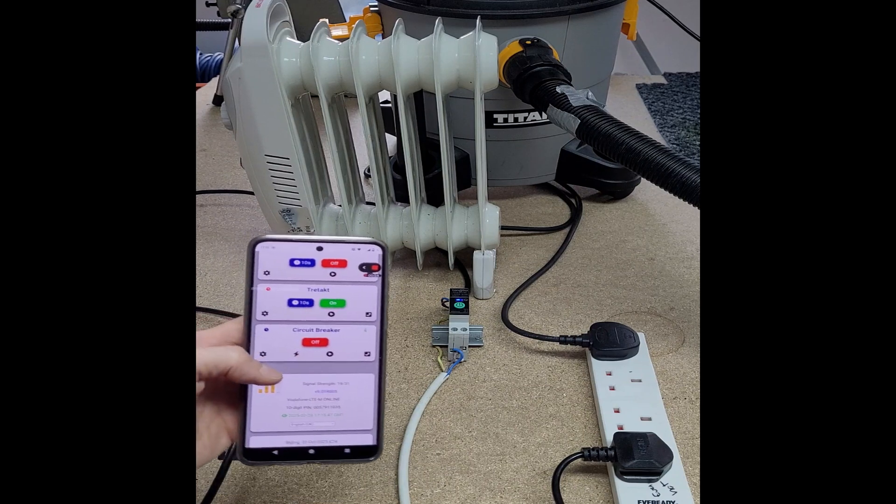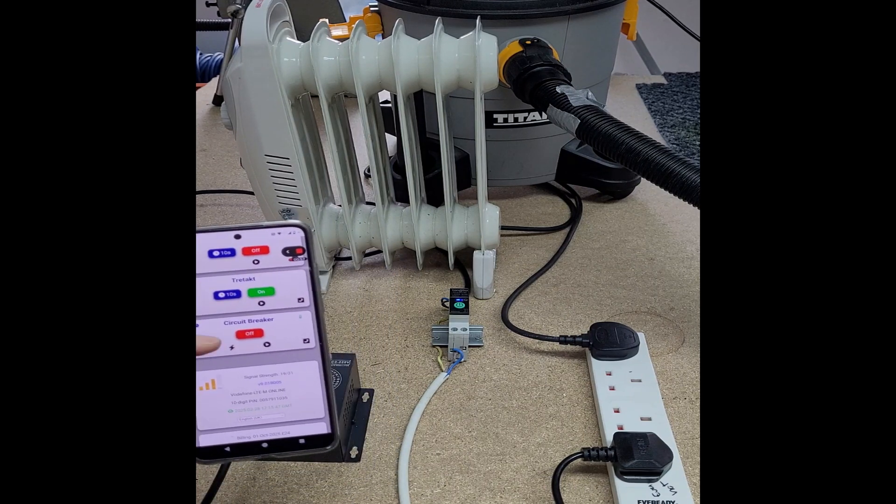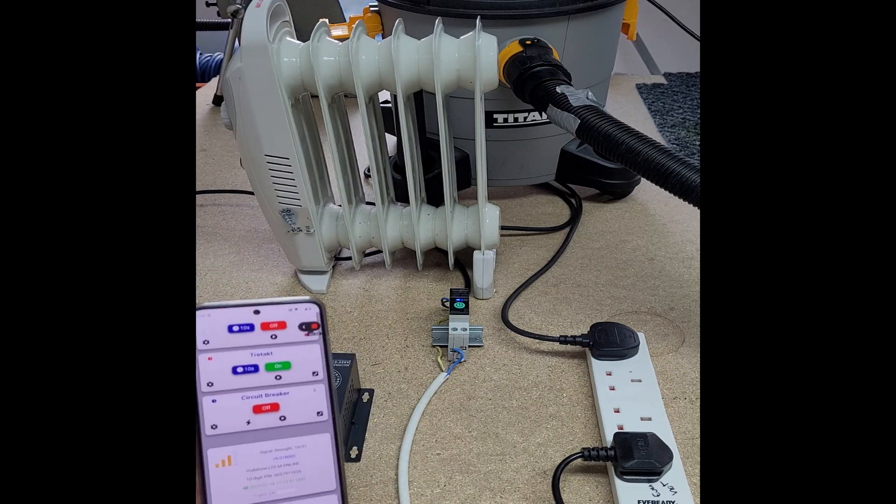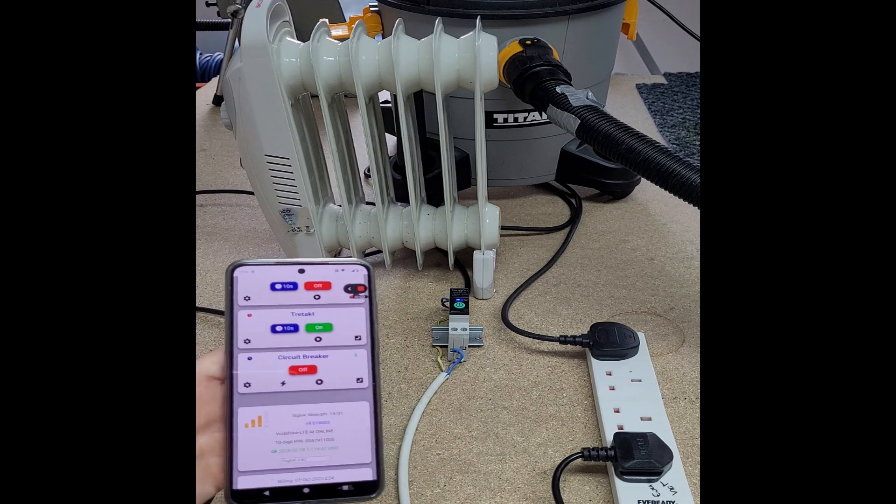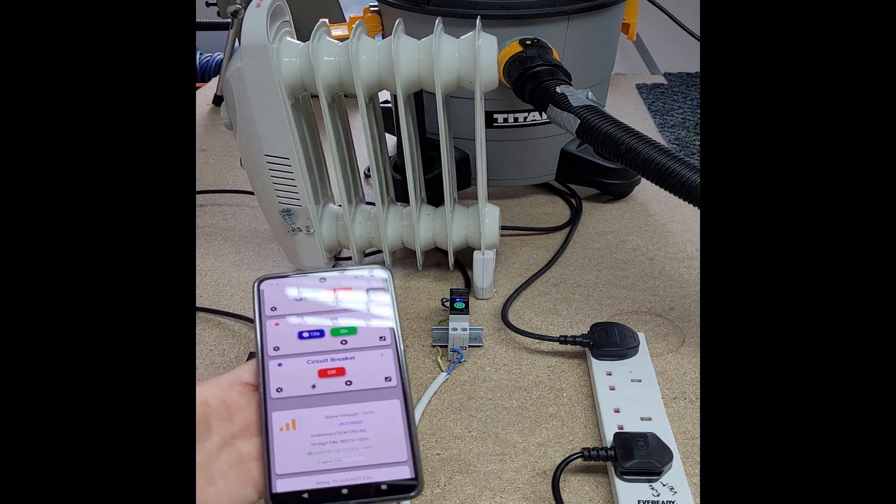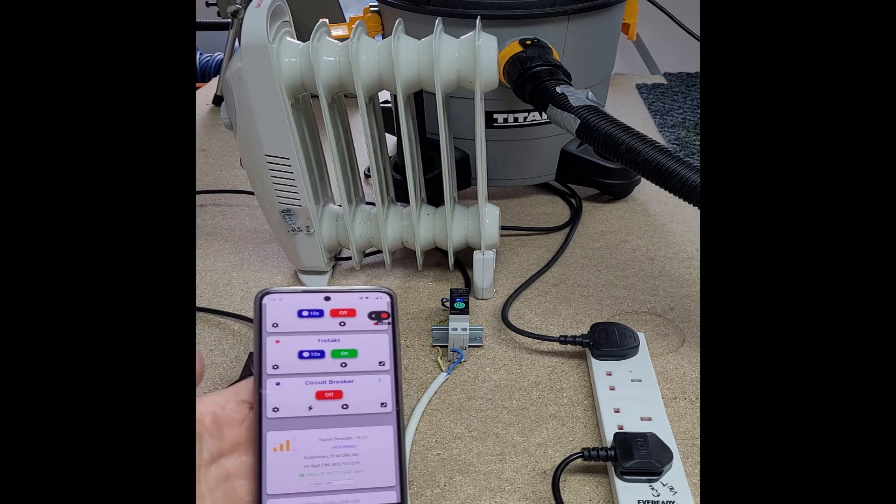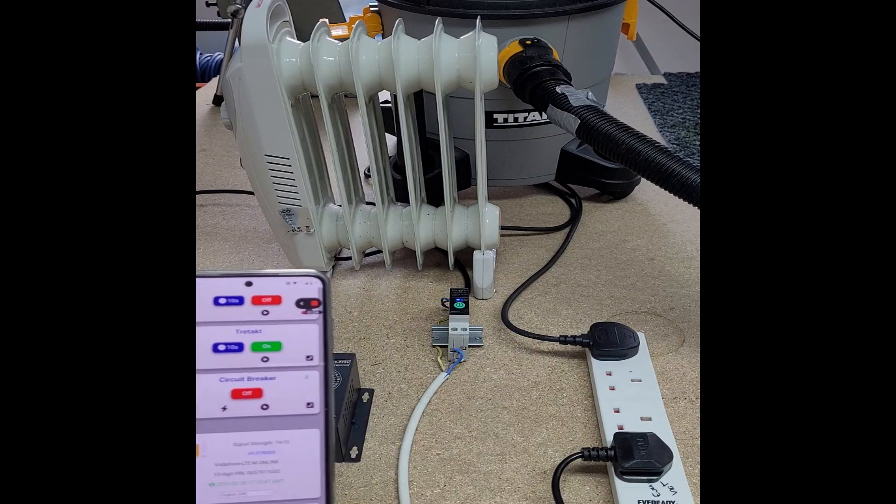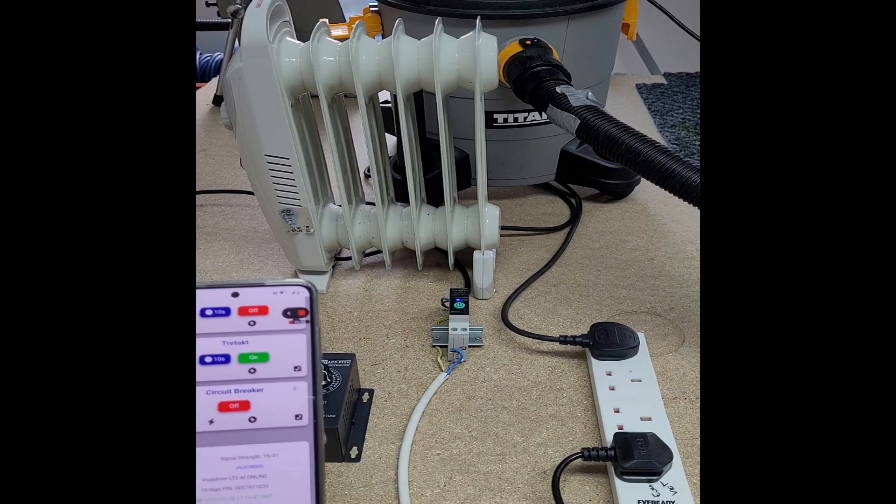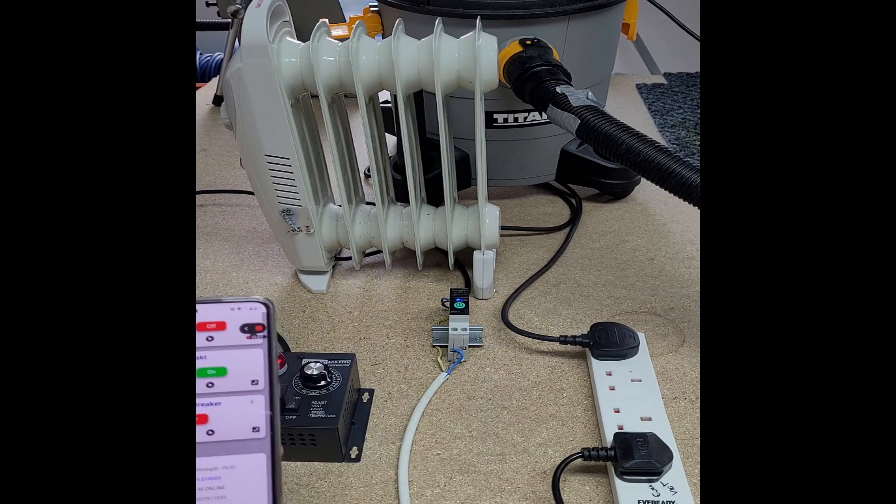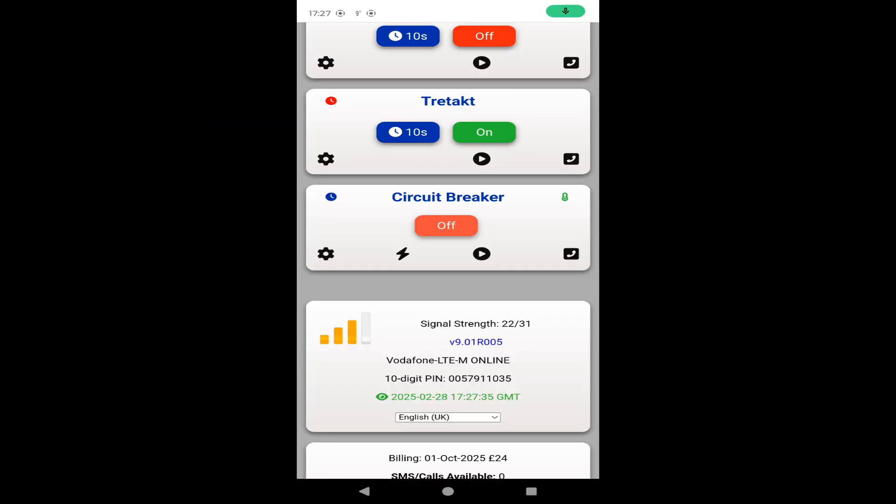There it is. The default name for that is actually circuit breaker, but not really circuit breakers - these are more high current switches with a software circuit breaker in them. If you're going to use them as a circuit breaker, put another circuit breaker in line of a higher current than you're going to set it to.